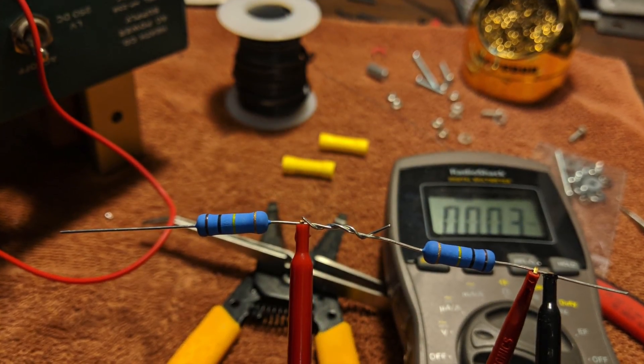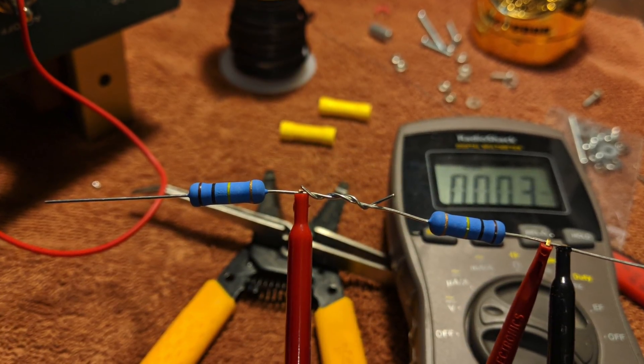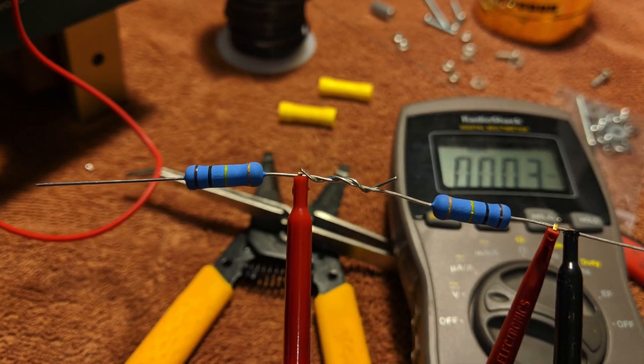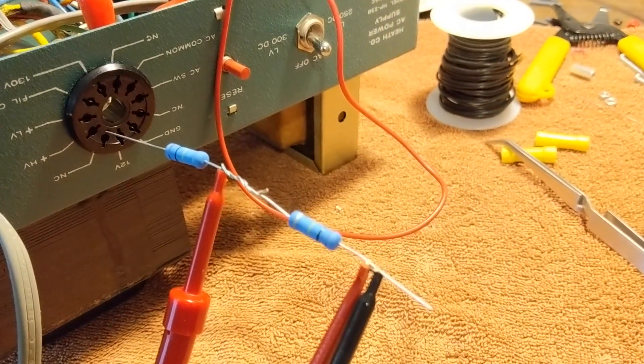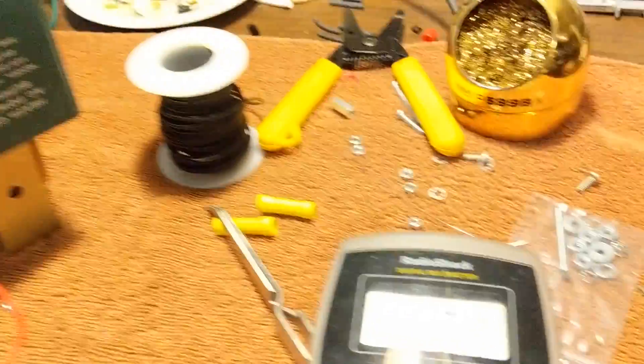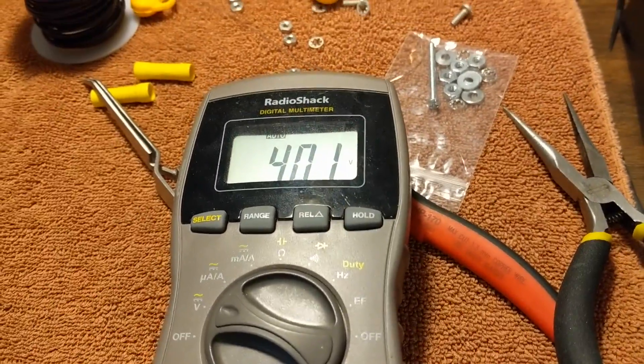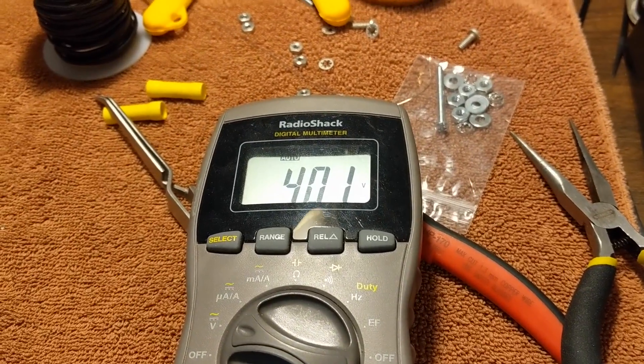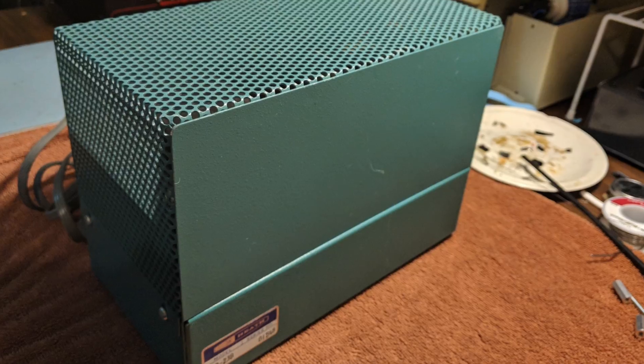In order to test that 800 volts — my multimeter will only test up to 600 volts — so I used a couple of 3 watt 100K resistors in series as a voltage divider, and was able to measure the 802 volts as 401 volts.